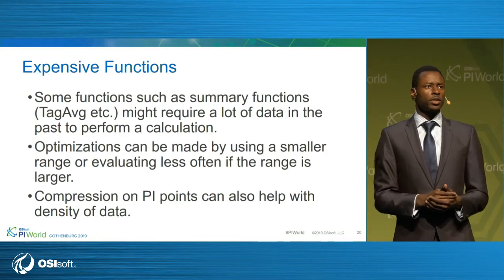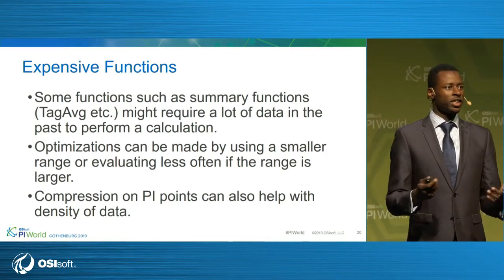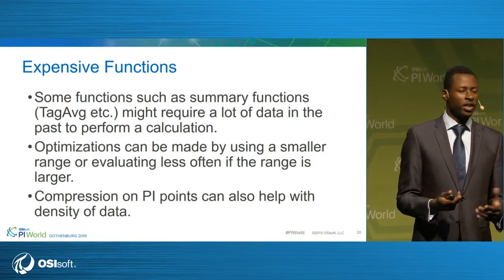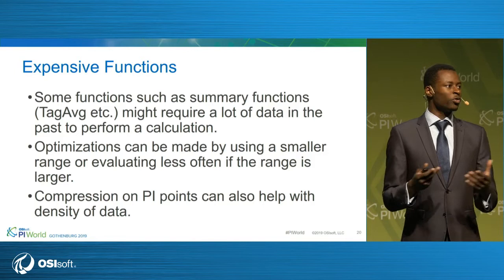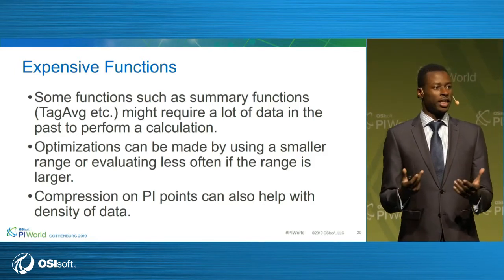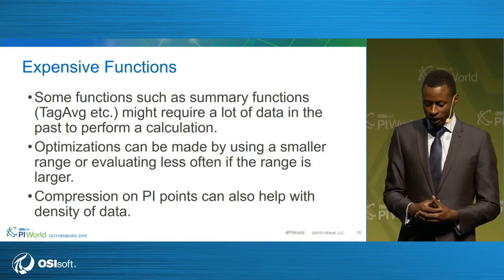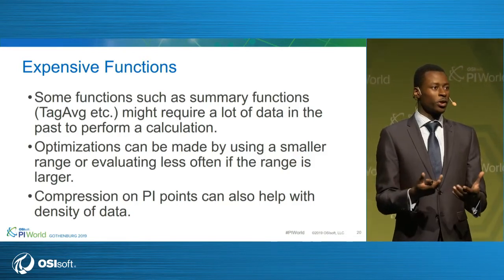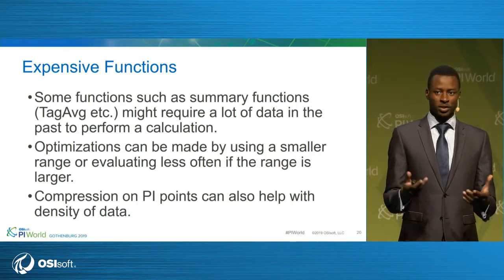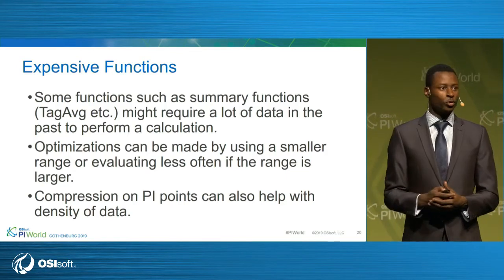Okay, so compression is really just an algorithm which is placed upon your time series data when it comes into the PI Data Archive. It allows you to neglect values which are not of interest. Maybe not enough change has happened for it to be stored within the PI Data Archive. So if you apply compression, you're allowing less data to be stored for those PI points, and therefore you can gain more out of it when it comes to doing the analysis in terms of performance.